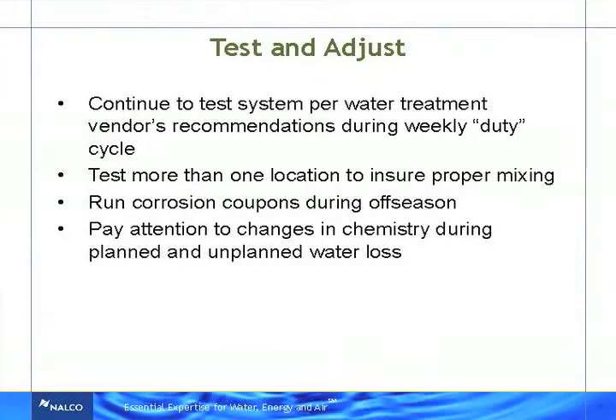Third thing, test and adjust. During the circulation period, you want to continue to test your water treatment because scale, corrosion, fouling, and microbial growth are still going to occur. So during that period, and typically you'll set it on your energy management system ahead of time, or maybe you'll just know that I'm going to bump the pumps for an hour every Wednesday at 3 p.m. or something like that. Also plan on doing your water treatment during that period. Grab samples, check your levels, check the bacterial levels, check your biocides, see what you need to be doing.